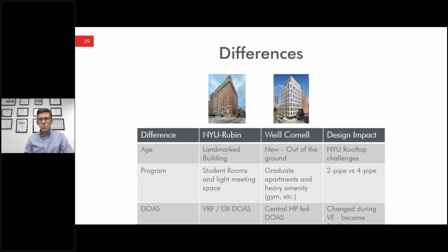And on NYU, it allowed us to create a fully two-pipe system because of the program. Whereas on Weill Cornell, we did have to provide a partial four-pipe system for those amenity spaces. And I'll talk a little bit about the differences there. And it did provide an additional complication. But obviously, the two-pipe versus four-pipe system is a pretty big difference in terms of cost. So we were mindful of that and tried to simplify that as much as we could for the residences themselves.